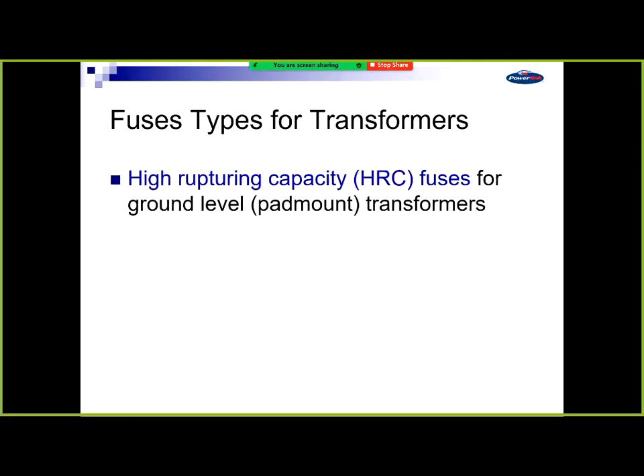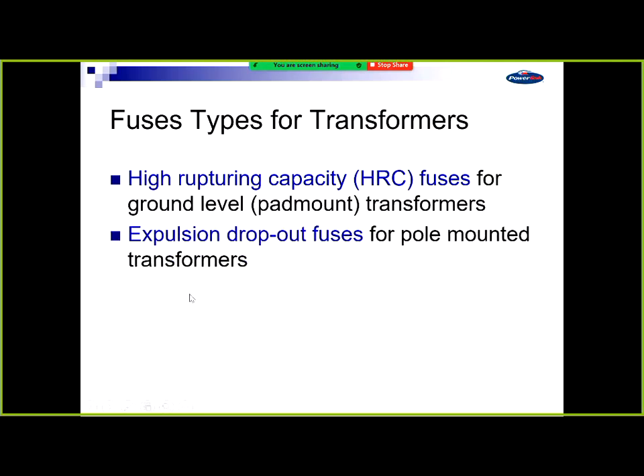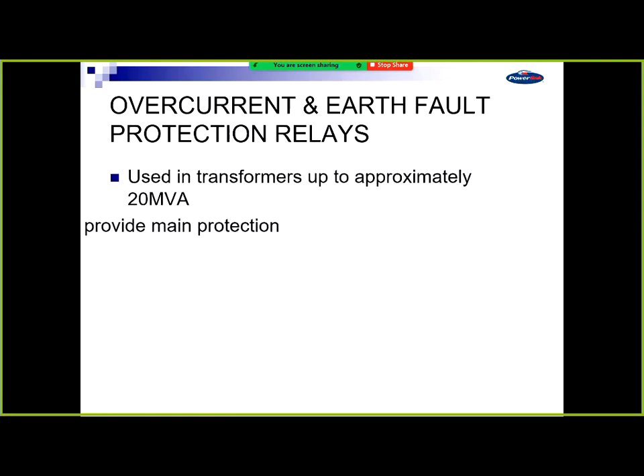Common ones are the high rupturing capacity fuse, the HRC. They're generally used for ground level pad mounted transformers. You can have the expulsion dropout fuses for pole mounted transformers. Next, as your transformers start to get a bit bigger, you can use an overcurrent and earth fault. That's what we used to use 25 or 30 years ago on these smaller transformers.